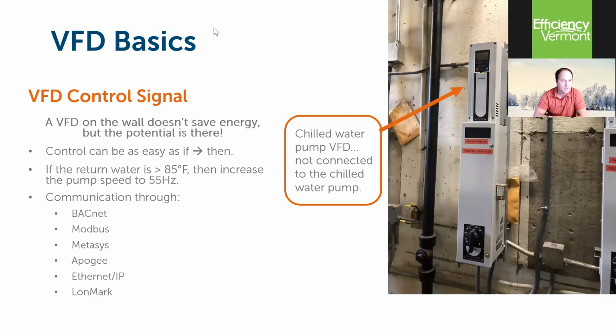There's a couple communication options typically with drives. There is a variety of drives out there, just like vehicles, there's sort of low, medium, high-end cars, just like there are drives. There's a lot of different communication, BACnet, Modbus, LonMark, a bunch of other ways of communicating from the drive back to a BMS or a SCADA system. Next slide, please.